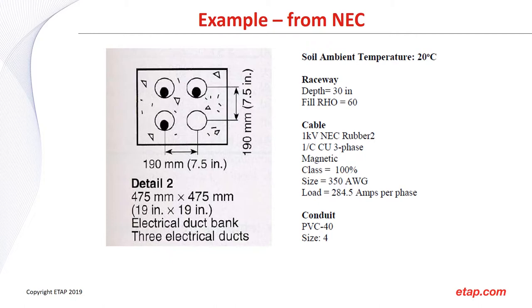The exercise we'll start with is an example from NEC — Detail Number 2, essentially a 2×2 configuration. We'll go over how to enter all the different dimensions: spacing between conduits, dimensions for the raceway, depth, thermal soil resistivity, cable characteristics, and conduit characteristics — which is PVC conduit size 4. We'll use the wizard to enter this information quickly.